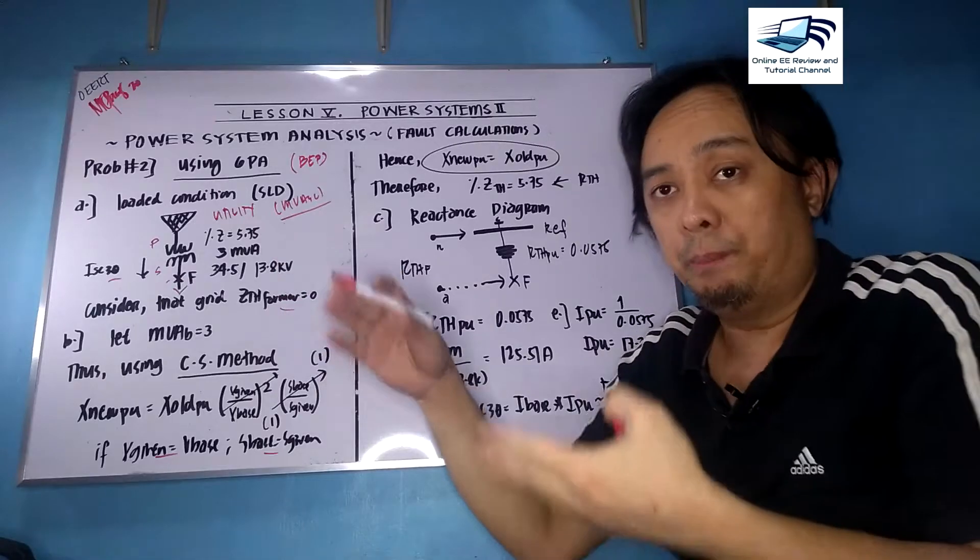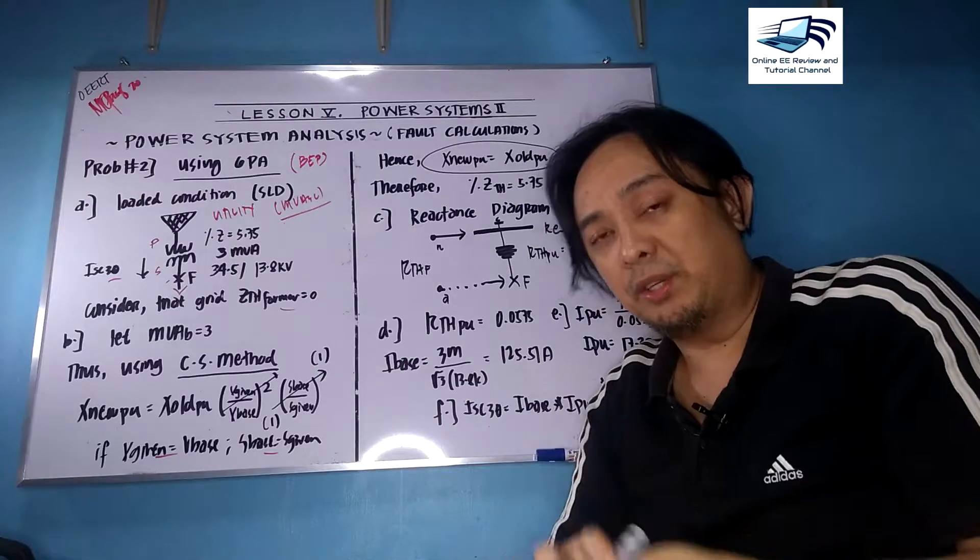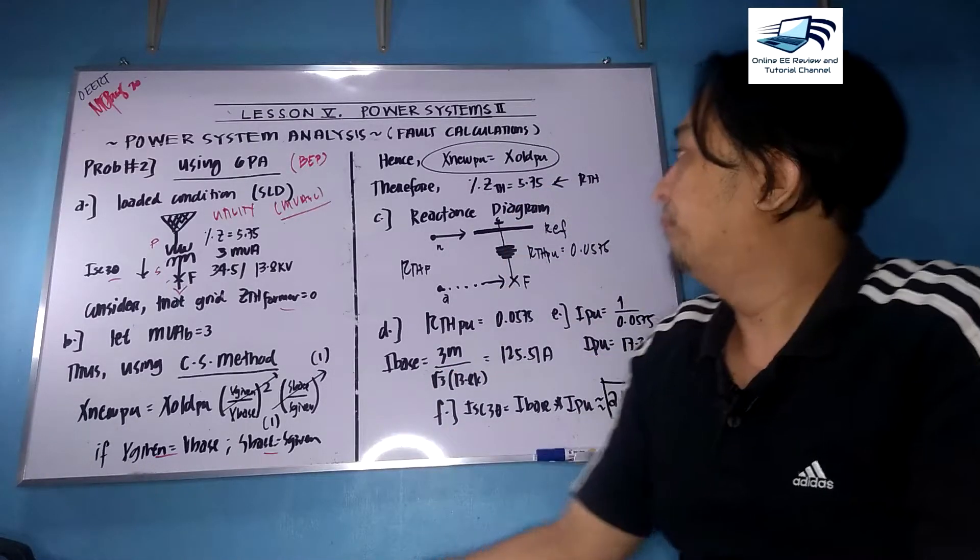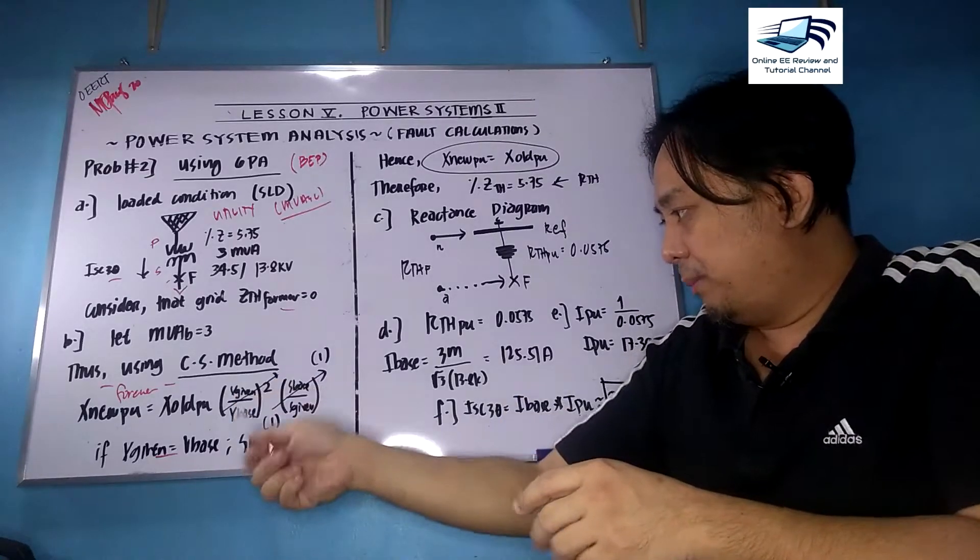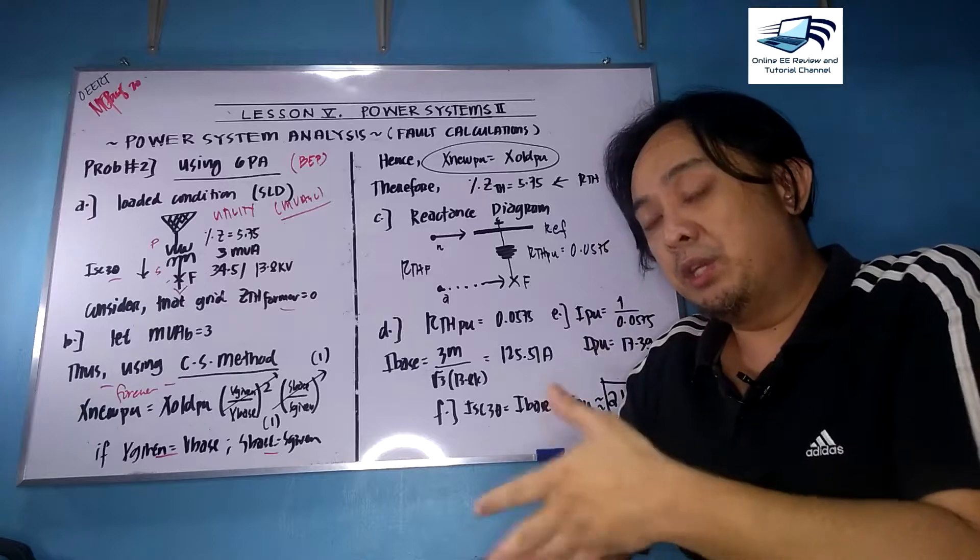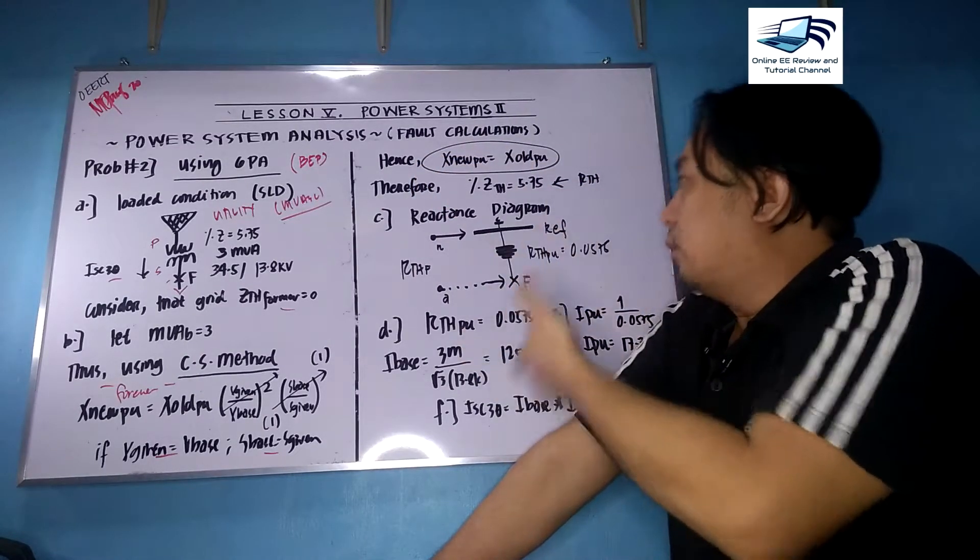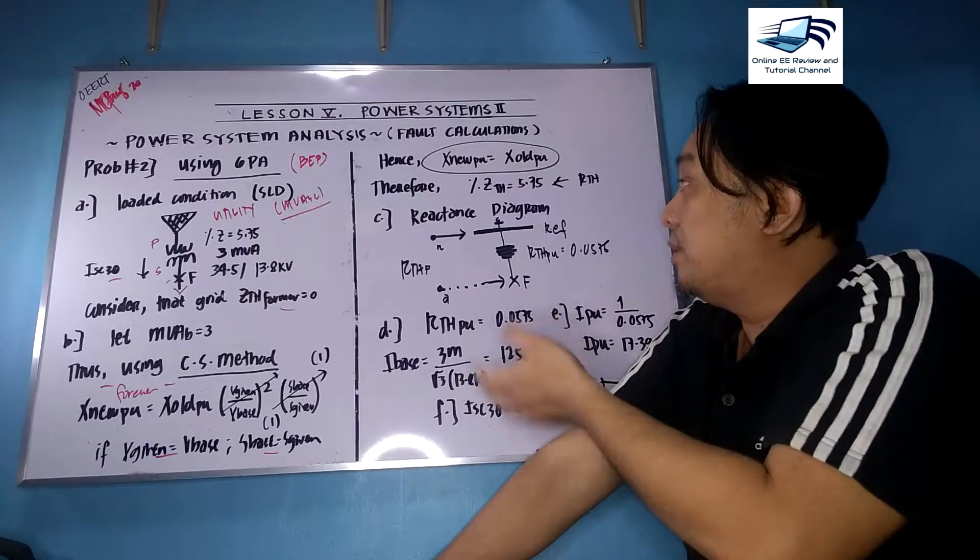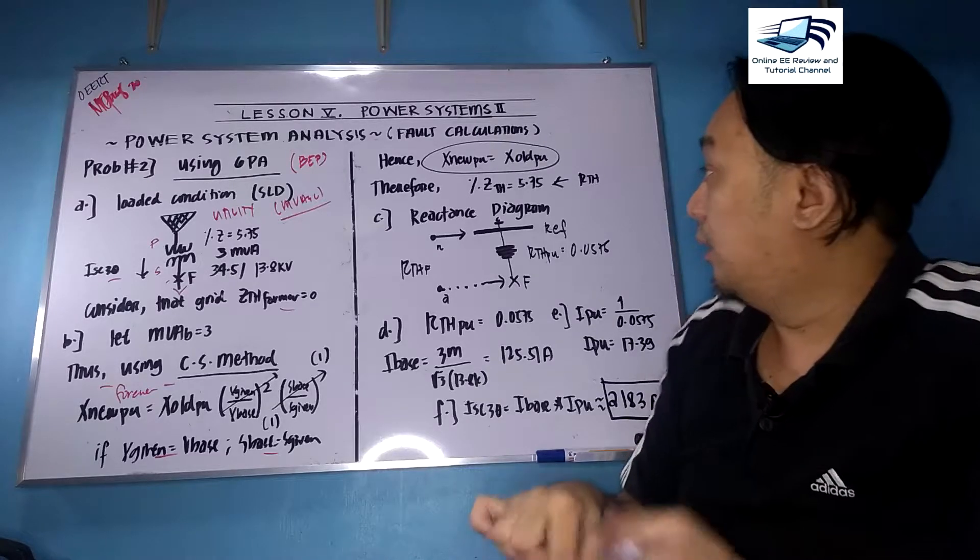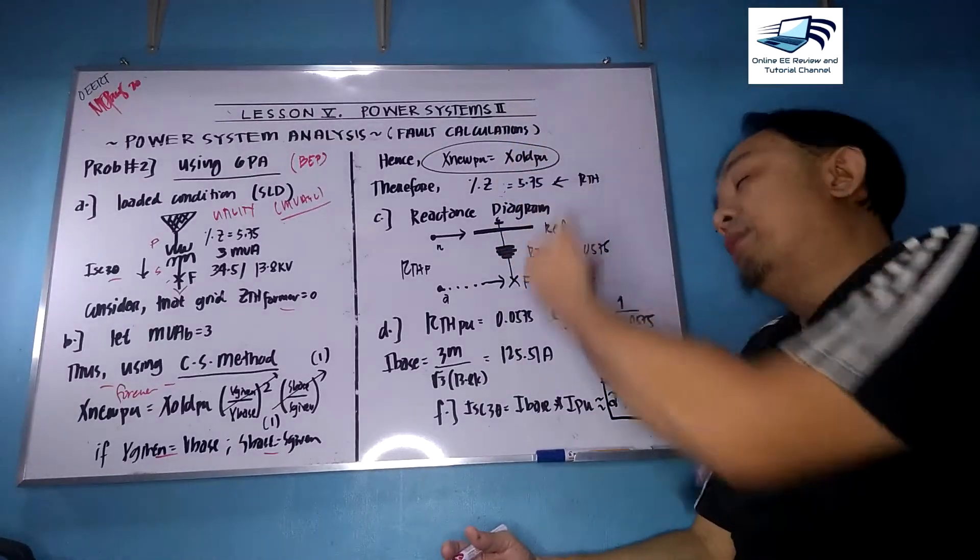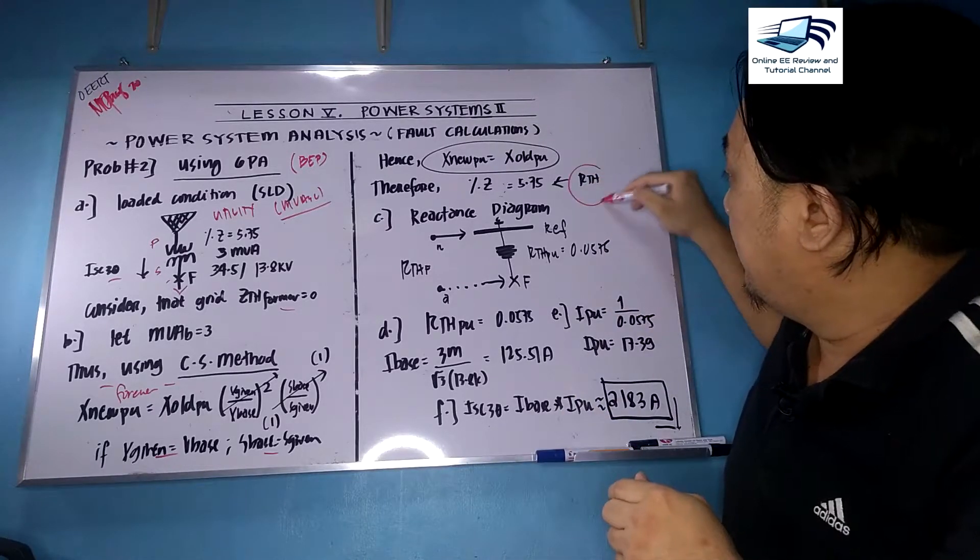From the forever formula, we can have V given and V base here, and S base and S given. They're equal to one. The Common Sense Method is: X_new equals X_old. It means whatever you're given is your new value of impedance, reactance, or resistance. In this case, we have the 5.75 percent impedance. The answer will be 5.75 as well. The percentage impedance is 5.75, which is also our RTH.